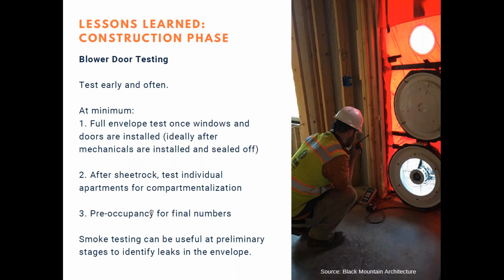We've talked about blower door testing a little, but there are typically several stages during construction when you need to run one. At minimum, you'll run one after windows and doors are installed to look at the overall envelope—a good place to use fog or smoke testing on any questionable areas that may have air leakage issues.